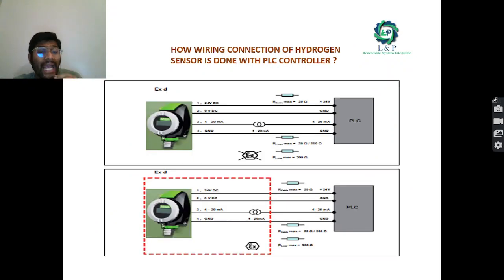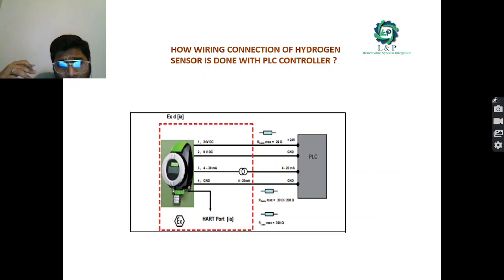So how can we do the wirings in the PLC controllers? So as we told earlier, we have 4 terminals inside it, 1, 2, 3, and 4. If you want to do the basic power supply, you can provide it to 0, 1, and 2. That is 24 volt DC power supply. Okay, and if you want to take the output, you can connect with the 3 and 4 terminals of the controllers. Okay, if you want to connect to the HART module also, we have a HART port here. There also you can make the HART port connections.